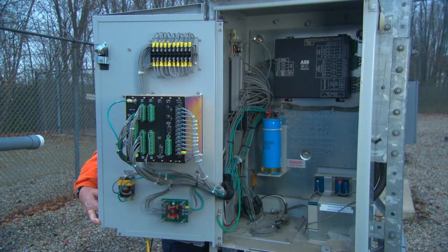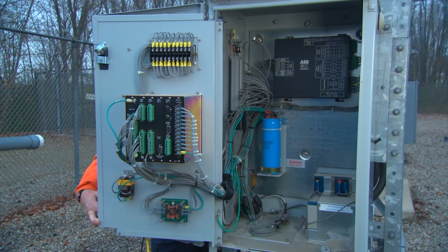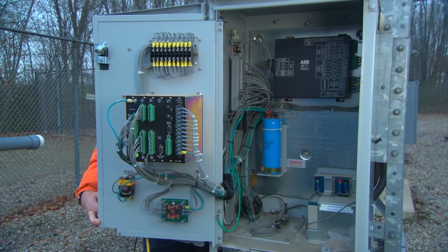Inside the back panel, you will see the interface on the control for connecting wet and dry contacts, a trip capacitor, and batteries and fuses along the edge, which are for the control and/or separate individual PT inputs if required. There is typically no need for a lineman to open the swing door on the control panel.